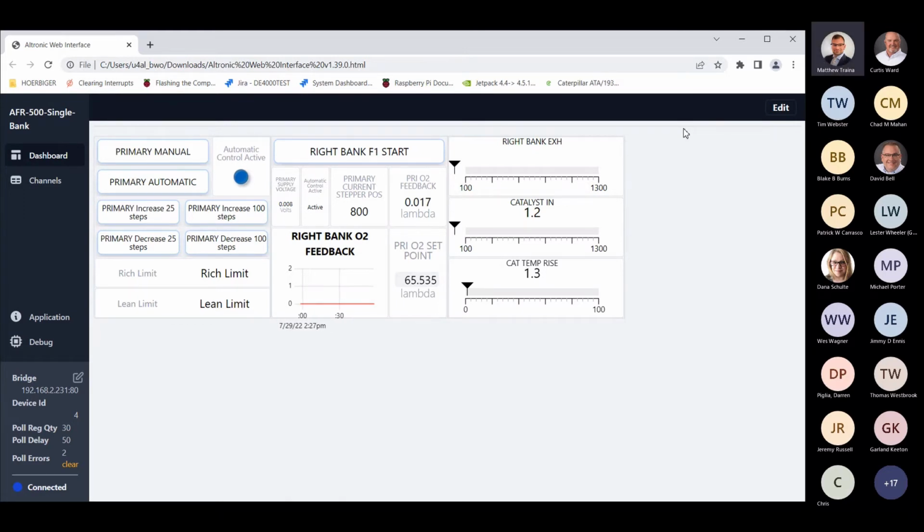just for a little bit of background, it's not going to be pinging each device, because that would kind of limit you in the future. So what it's actually doing is asking the ACM, what data do you have? And then if it doesn't have it, the gateway will go get it and respond to what's trying to draw the graphs. So when you do that, if you have this big collection point from 95s, DETs, VSMs, DE-4000, you name it, right? It's collecting it and putting it in a database.